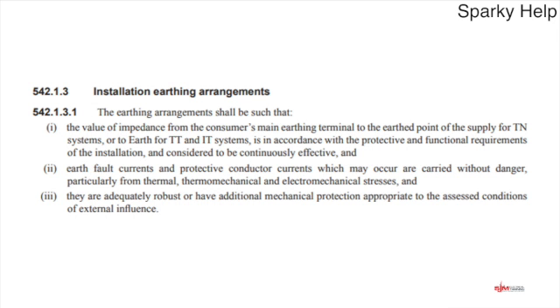So why do we earth? The installation earthing arrangements, this is from our regulations, as you can see from 542.1.3, lots of numbers. The earthing arrangements shall be such that, and you've got to meet these 3 requirements: the value of the impedance from the consumer's earthing terminal to the earth point of the supply for TN systems; earth fault currents and protective conductor currents which may occur are carried without danger, particularly from thermal, thermomechanical and electromechanical stresses; and number 3, they are adequately robust or have additional mechanical protection appropriate to the assessed conditions of external influences. So we may need to put additional protection around them if the earths or CPCs or the green and yellow cables aren't necessarily big enough. So that's what we're required to do.